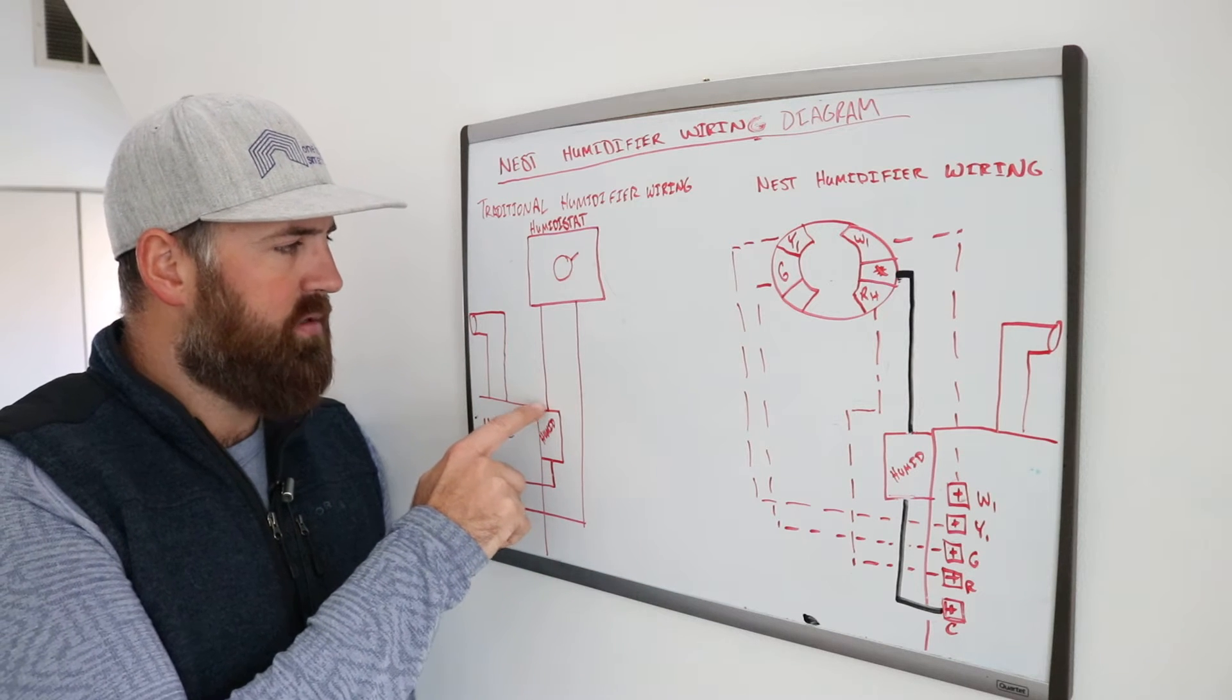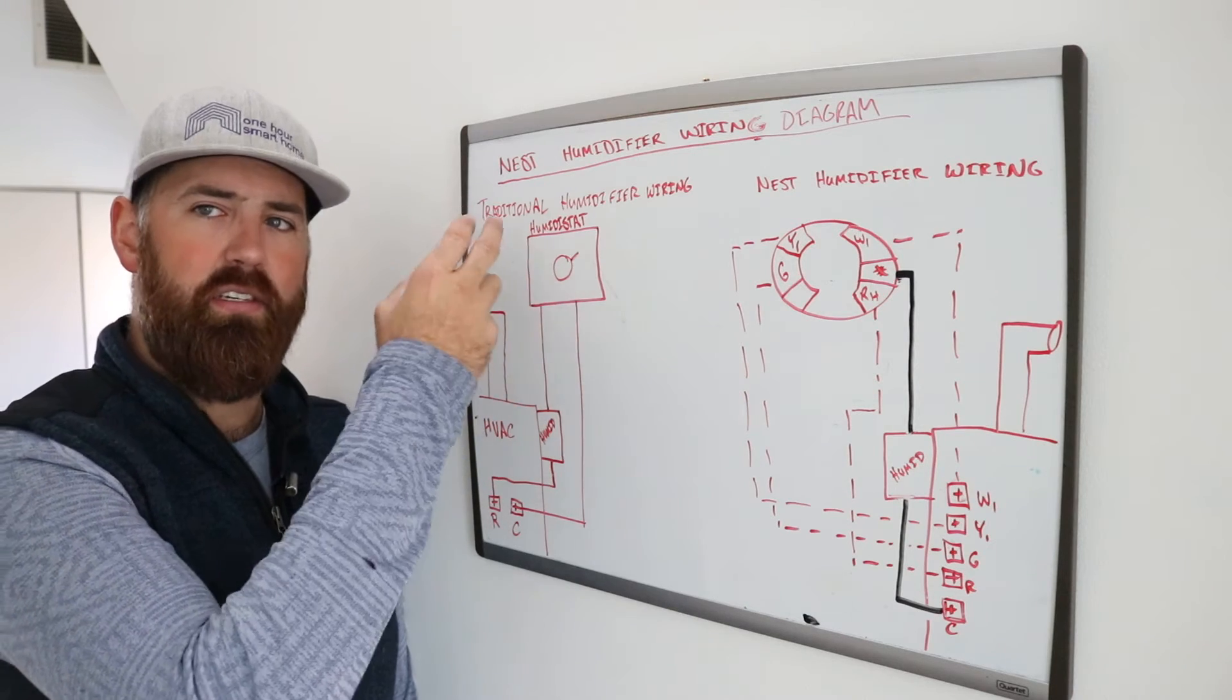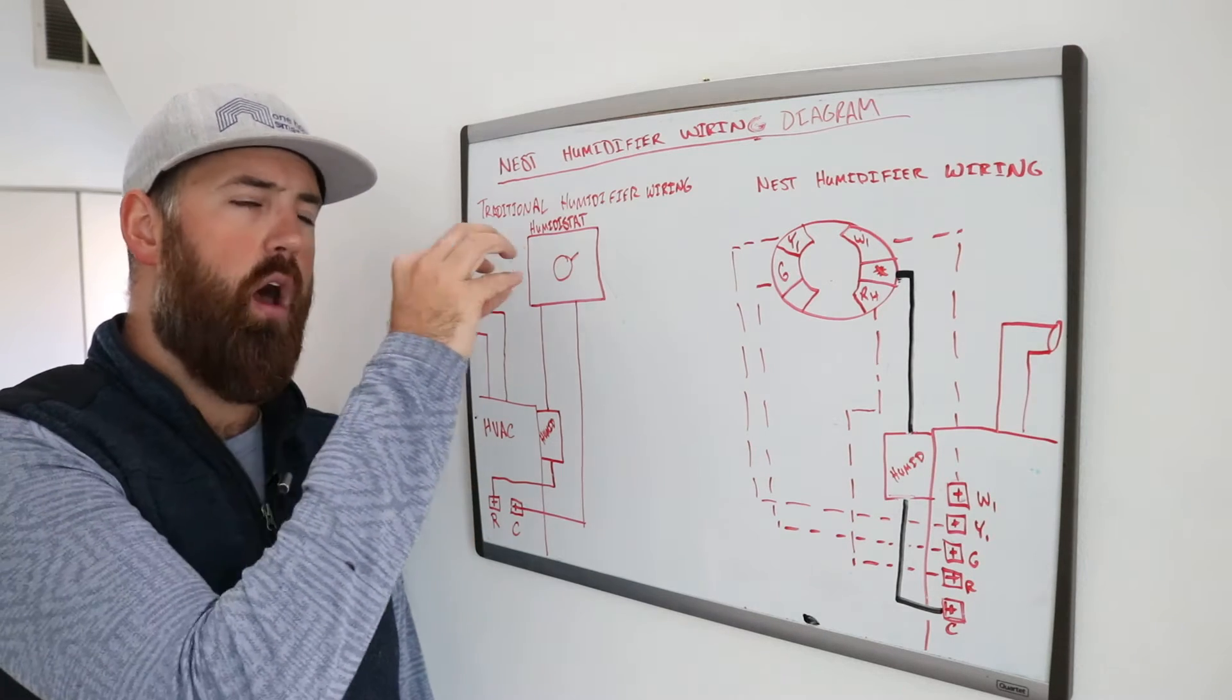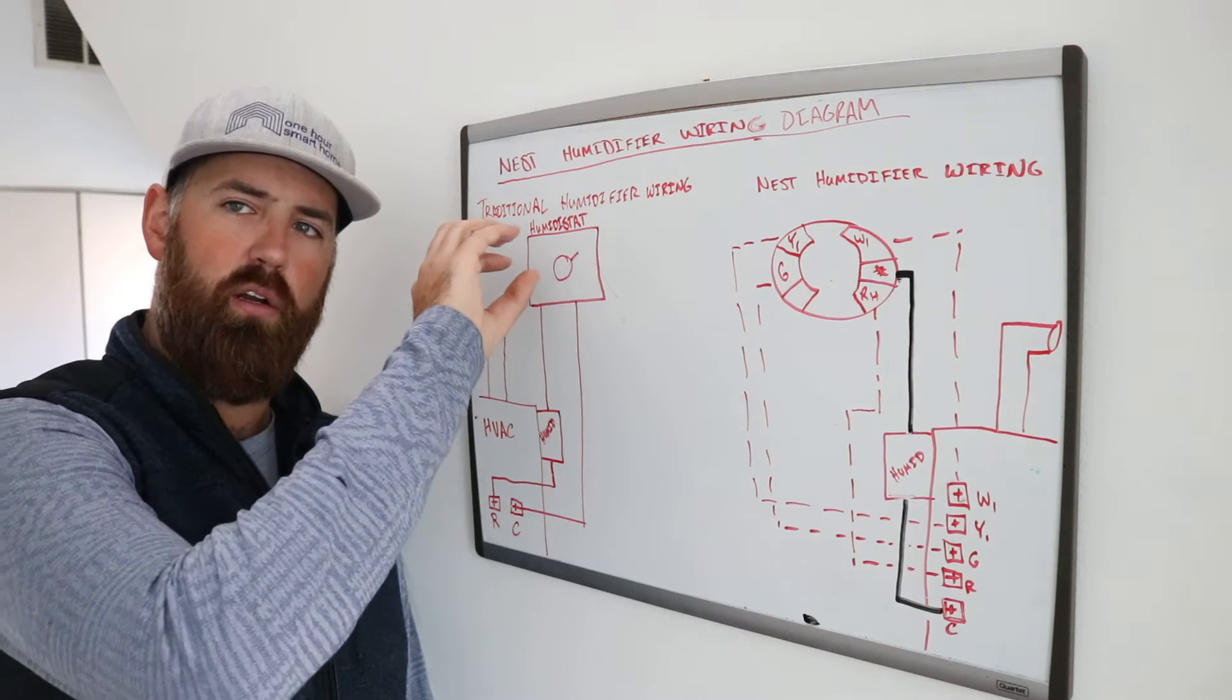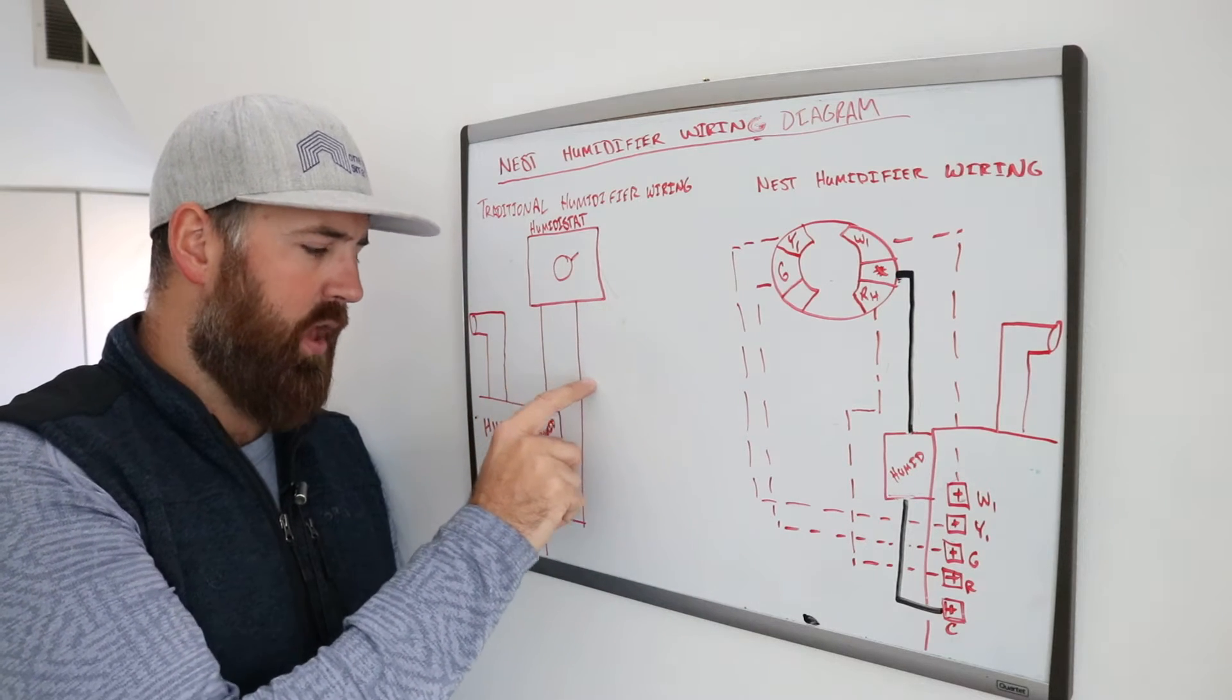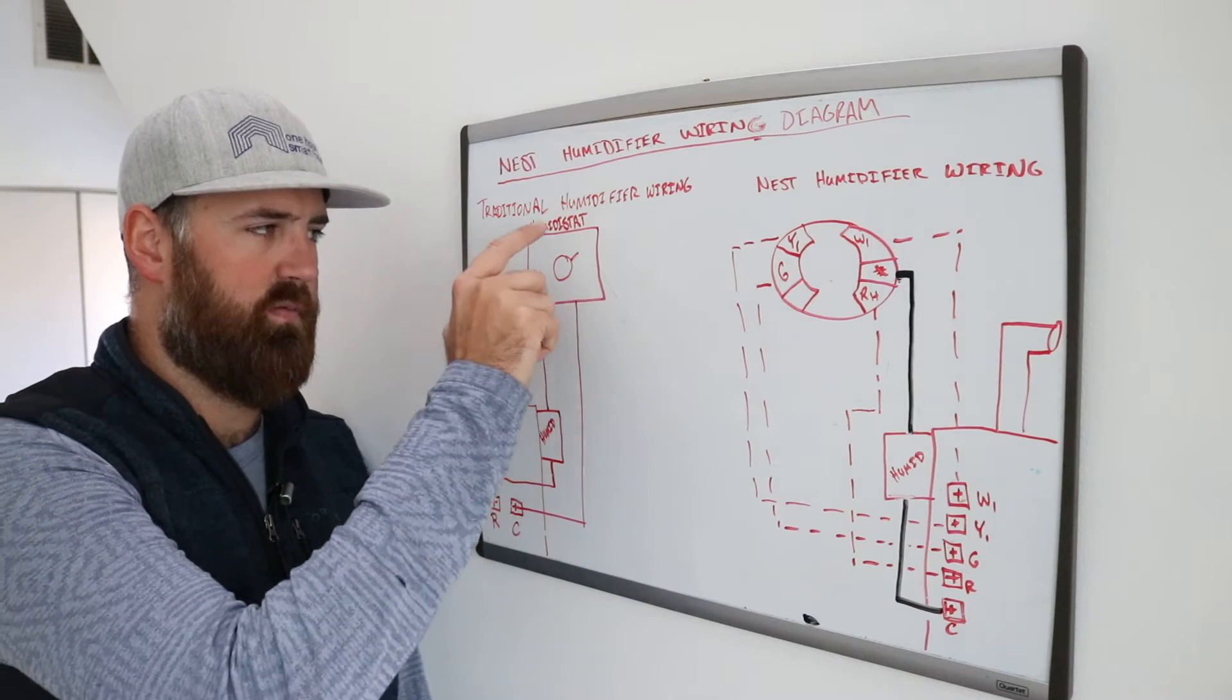And the power goes through the humidifier and to the humidistat which controls the humidity. And all this is is an open close switch really. When the humidity is too low and you've got the humidifier set higher, it's going to close that switch, create a circuit so you'll have power going through the humidifier, down through the humidistat and back to the C terminal, it creates a full circuit here.